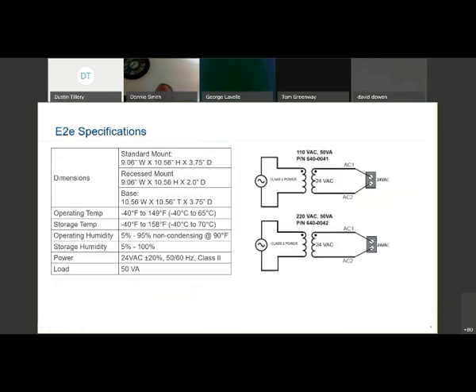As for the specifications, what you need to know here is really the power that it takes. It runs off a 24 volt AC class 2 transformer, but it must be a minimum of 50 VAs. So anytime you're selling these out in the field, be sure your customer has the proper power going to it in the form of a 50 VA transformer.